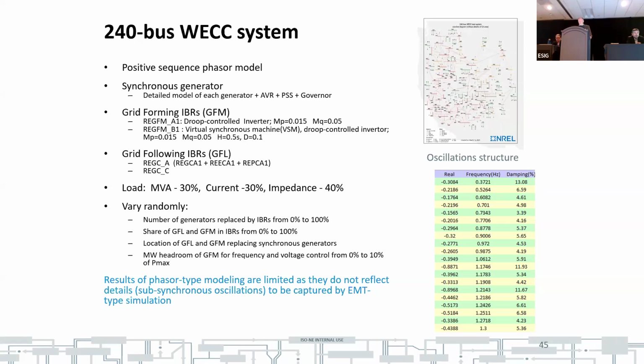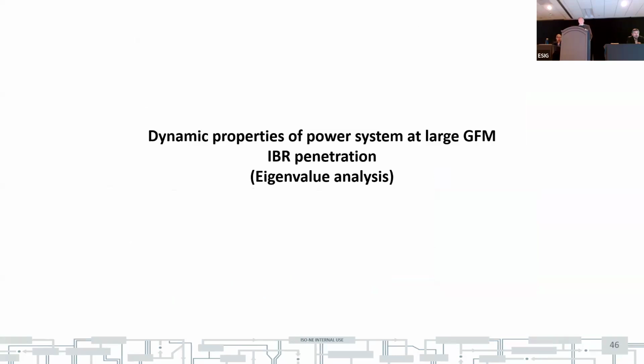So for the study, it was a type of Monte Carlo simulation where an arbitrary number of generators were replaced by inverters with a random combination of grid forming and grid following. And also important, the headroom for control on grid forming inverters was varied from 0 to 10%. So the results of this study are as good as the positive sequence model of the inverter. So that is a limitation.